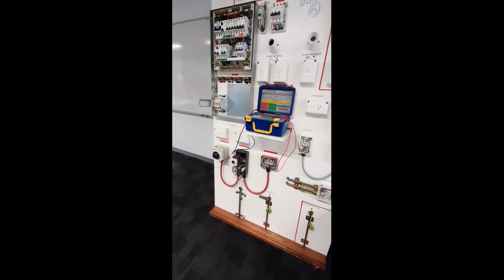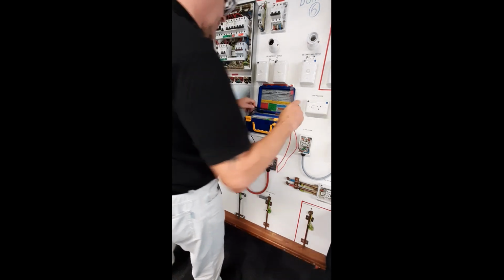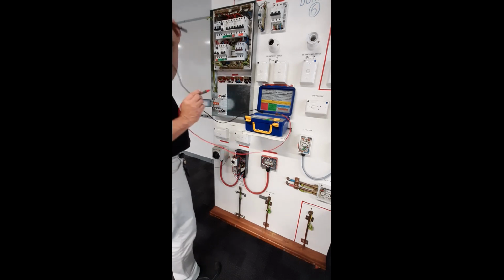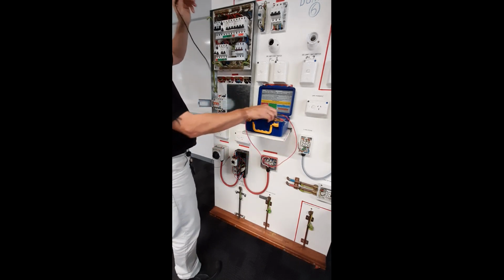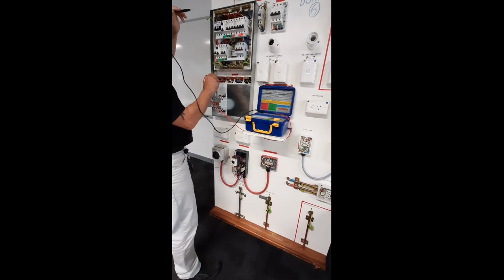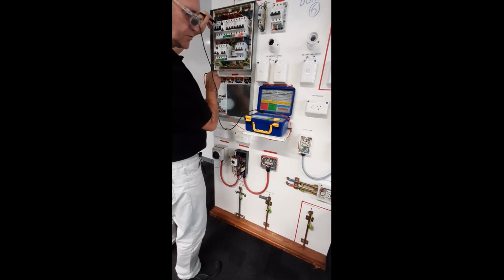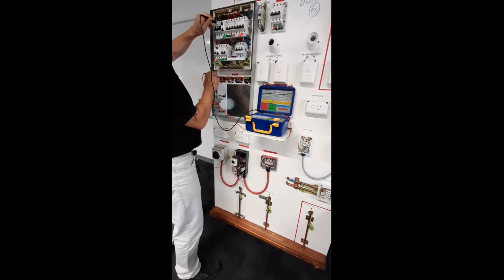Polarity test of the consumer main. The point-to-point method is recommended for the consumer main. Starting at the start of the consumer mains and going all the way up to the main switch. The red phase, I have continuity, approximately 0.05 of an ohm. Confirm that it's not in the white phase or transposed at all to the blue phase.